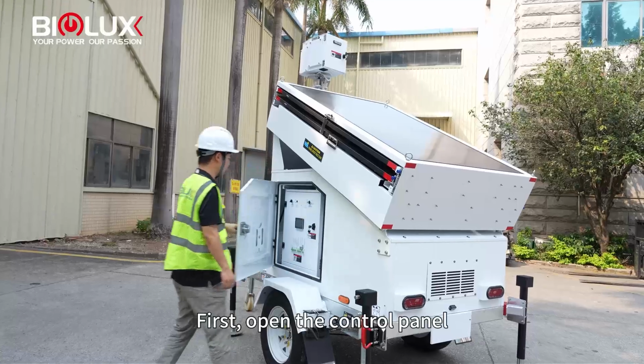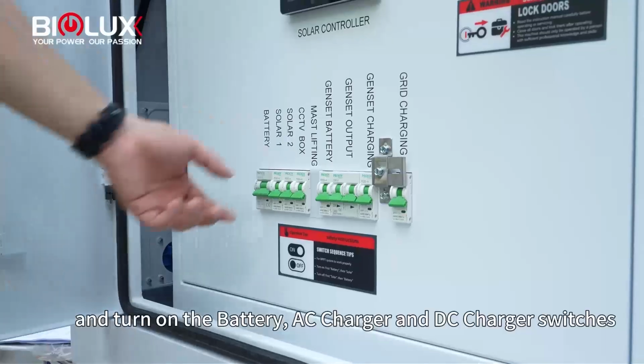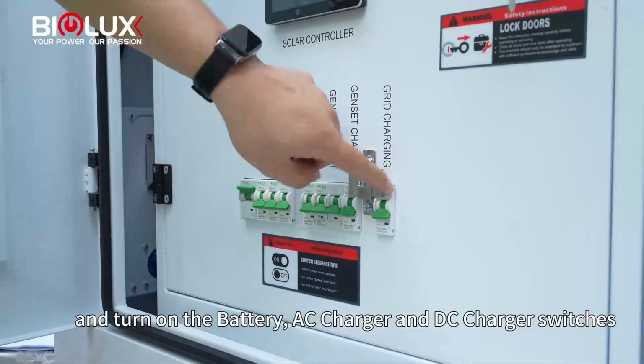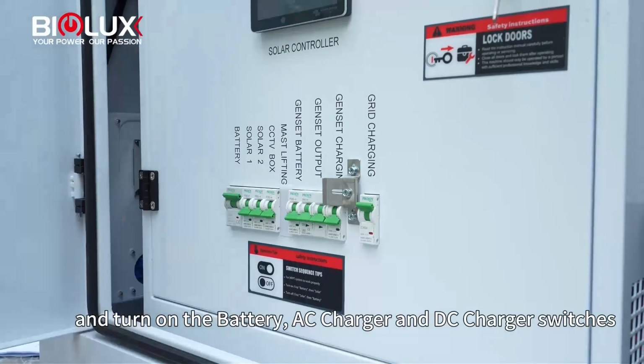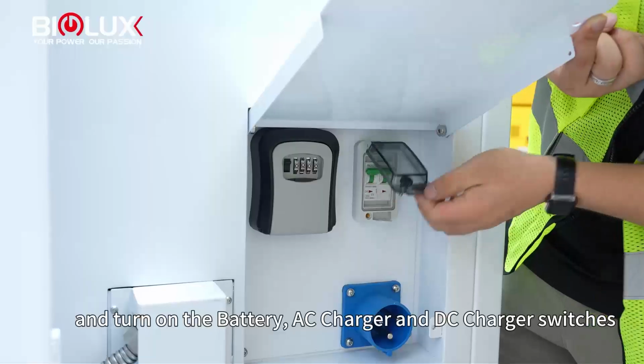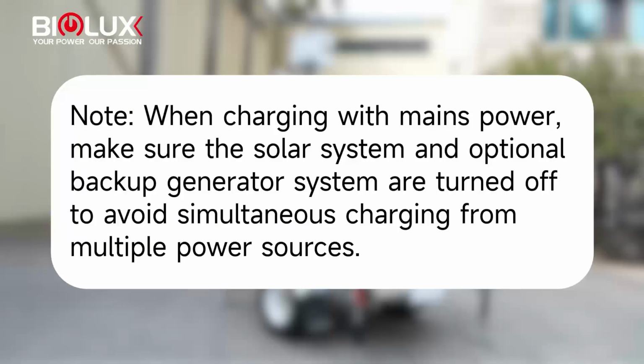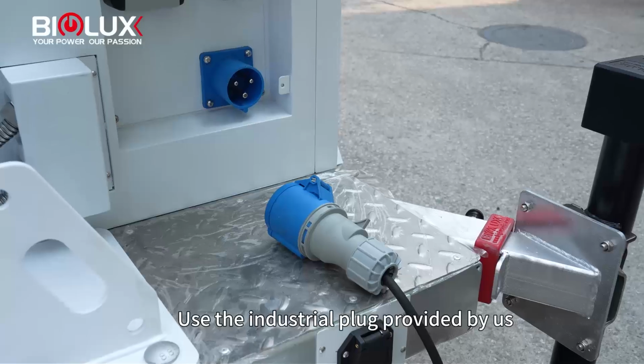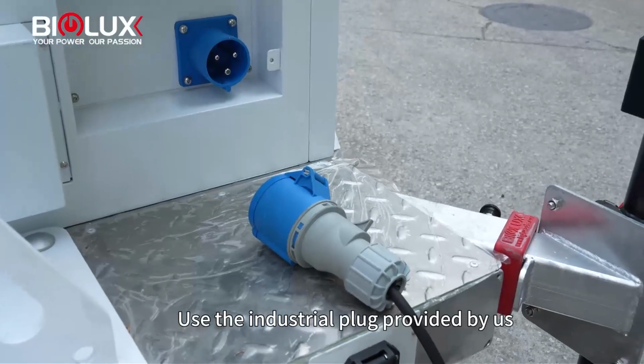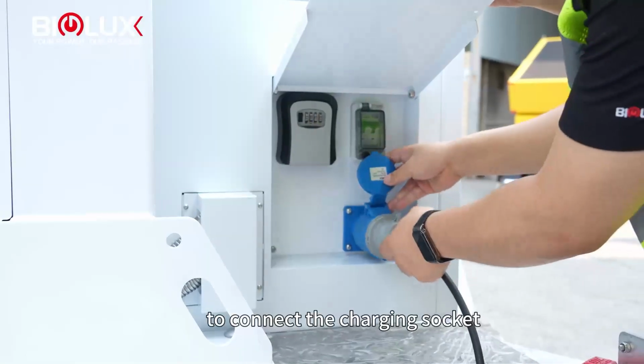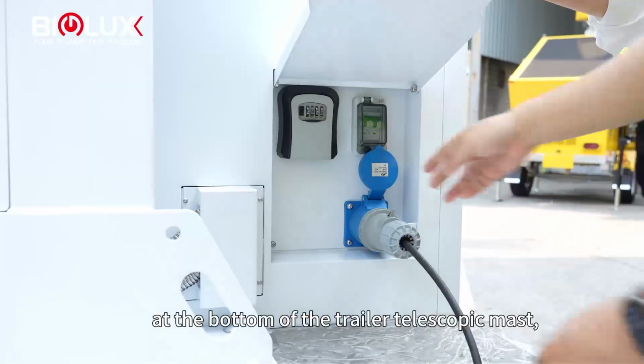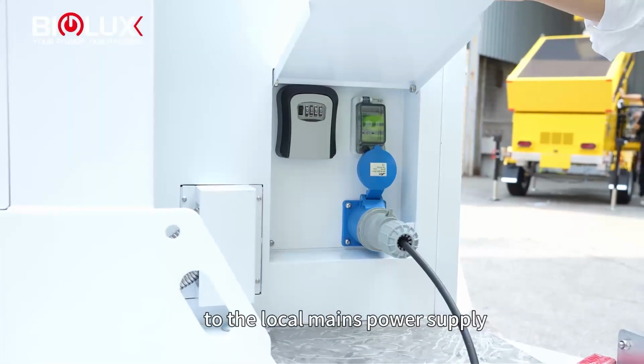First, open the control panel and turn on the battery, AC charger and DC charger switches. Note, when charging with mains power, make sure the solar system and optional backup generator system are turned off to avoid simultaneous charging from multiple power sources. Use the industrial plug provided by us to connect the charging socket at the bottom of the trailer telescopic mast to the local mains power supply.